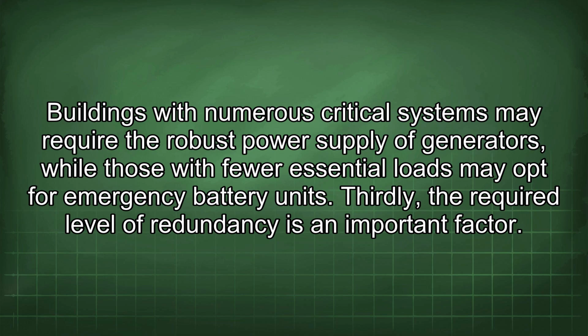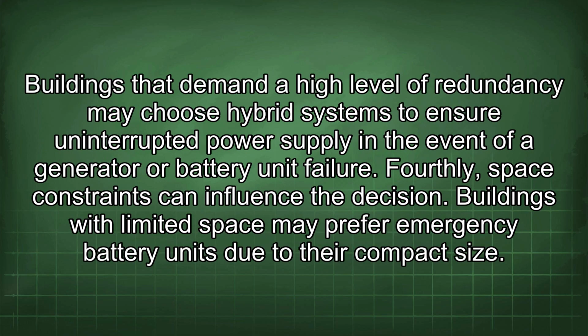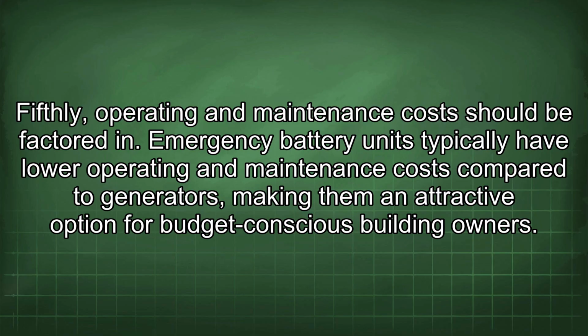Thirdly, the required level of redundancy is an important factor. Buildings that demand a high level of redundancy may choose hybrid systems to ensure uninterrupted power supply in the event of a generator or battery unit failure. Fourthly, space constraints can influence the decision. Buildings with limited space may prefer emergency battery units due to their compact size. Fifthly, operating and maintenance costs should be factored in. Emergency battery units typically have lower operating and maintenance costs compared to generators, making them an attractive option for budget-conscious building owners.